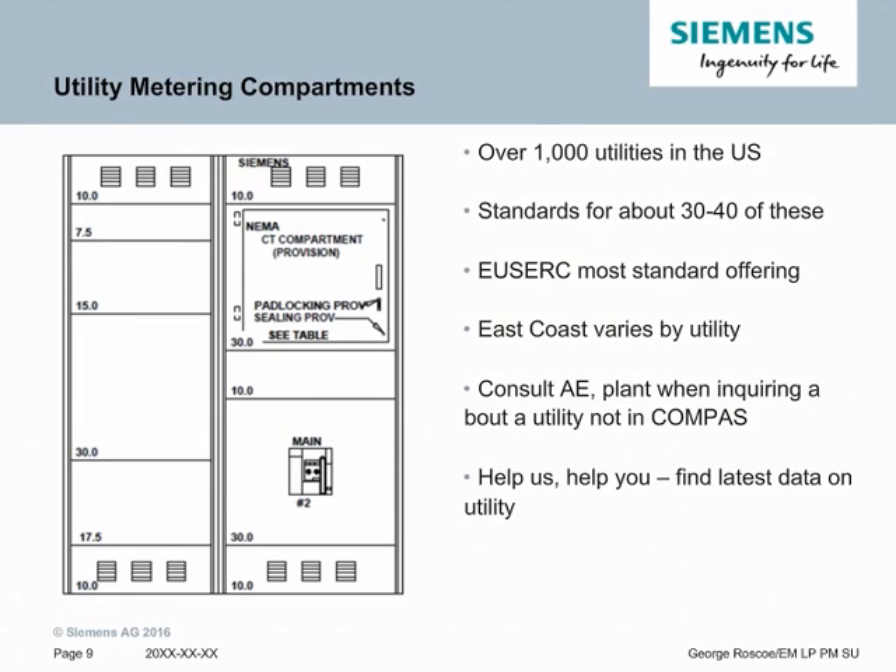Let's talk a little bit about utility metering compartment design. The image on the left shows a hot sequence utility design. Power comes in on the left section, then runs through the NEMA CT compartment to the main breaker. This is called hot sequence metering — the meter is in front of the main. If the metering is under the main, we call that cold sequence metering. This depends completely on the utility's design. Right now there are over 1,000 utilities in the United States, and Siemens currently has standards for about 30 or 40 of these. EUSERC has the most standard offering, so most of the West Coast is covered under a handful of standard designs, allowing them to be mostly SB2 or SB1 boards. For the rest of the country, we have about 38 designs that allowed it to be SB2. The rest would be considered SB3 because there are custom utility designs.